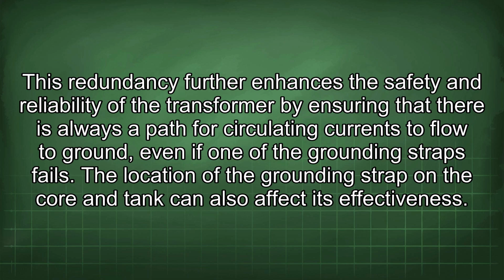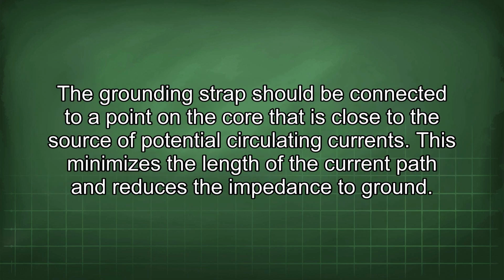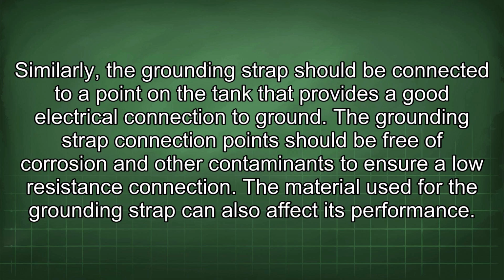The location of the grounding strap on the core and tank can also affect its effectiveness. The grounding strap should be connected to a point on the core that is close to the source of potential circulating currents. This minimizes the length of the current path and reduces the impedance to ground. Similarly, the grounding strap should be connected to a point on the tank that provides a good electrical connection to ground. The grounding strap connection point should be free of corrosion and other contaminants to ensure a low resistance connection.